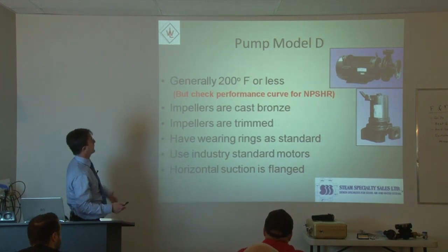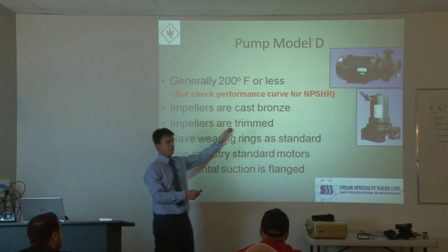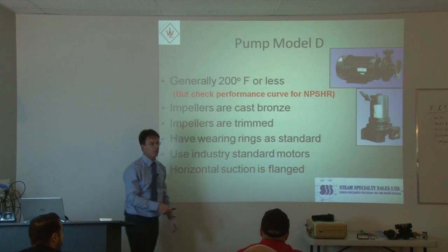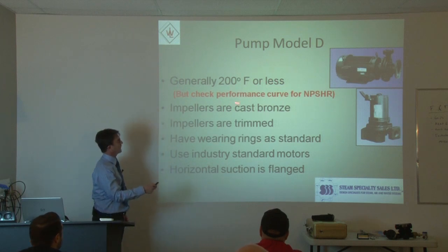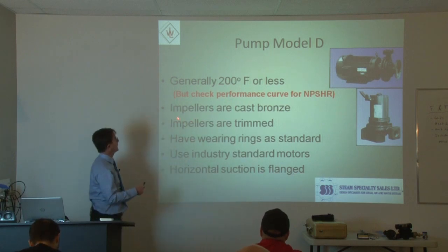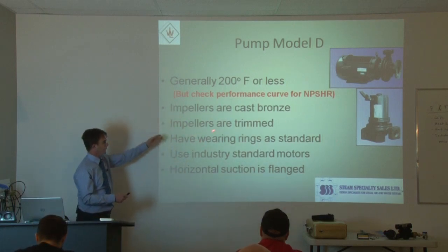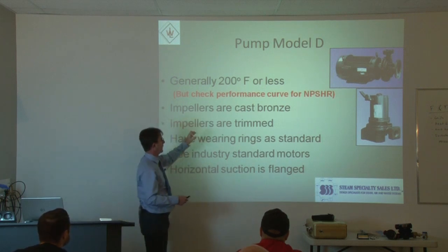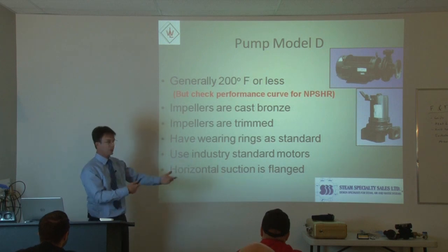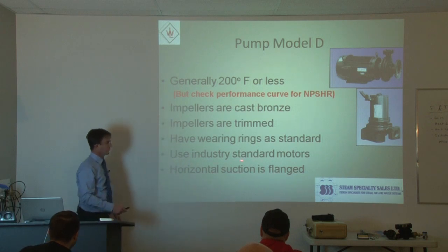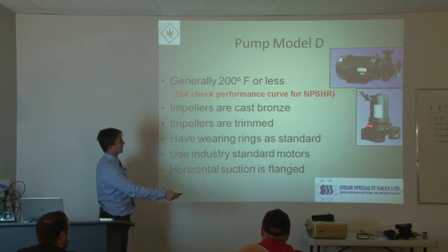Pump Model D is generally for 200 degrees Fahrenheit or less, but check the performance curve. Net positive suction head required - NPSHR - is just the amount of pressure required for the pump to operate properly. It's generally for lower temperatures, but we have to make sure the pump is still operating on its curve. Impellers are all cast bronze - no plastic impellers. All Shipco pumps have cast bronze impellers, trimmed to the actual load required. They have wearing rings as standard, so the ring wears before the impeller does and can be replaced independently - a cost-saving feature. Shipco only uses industry standard motors, so you don't need a specialized motor from Shipco.